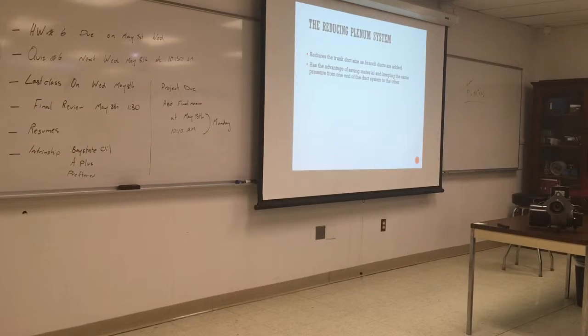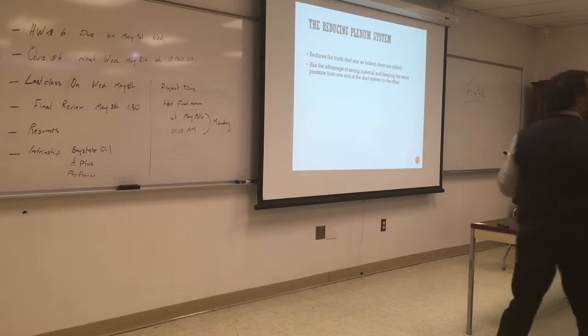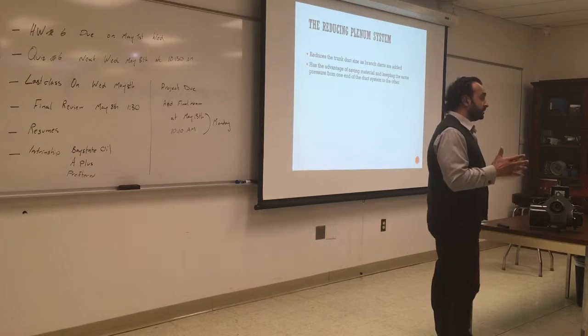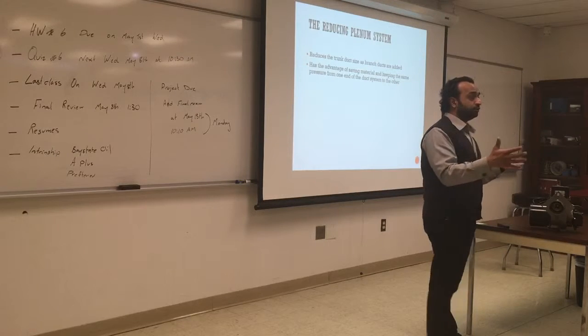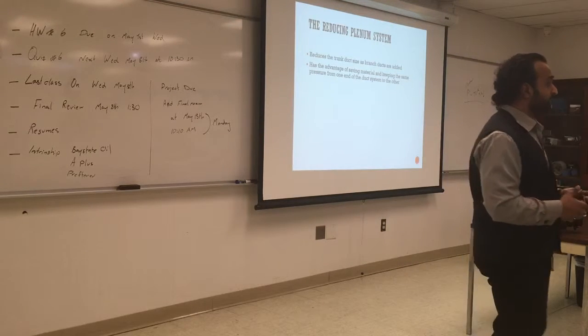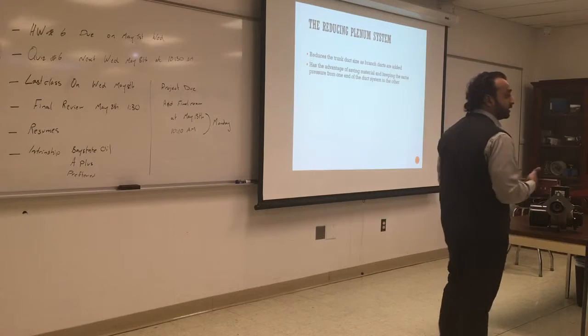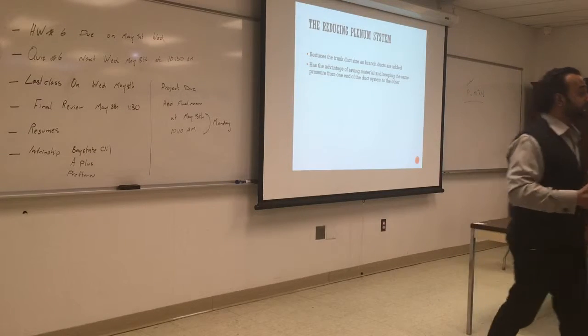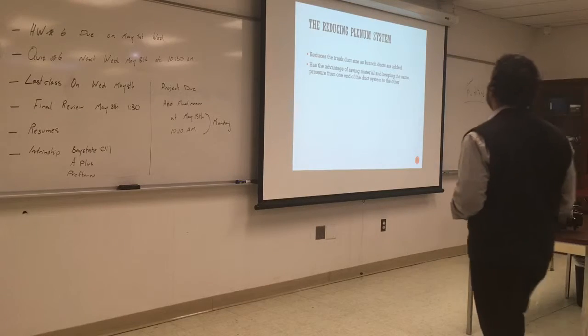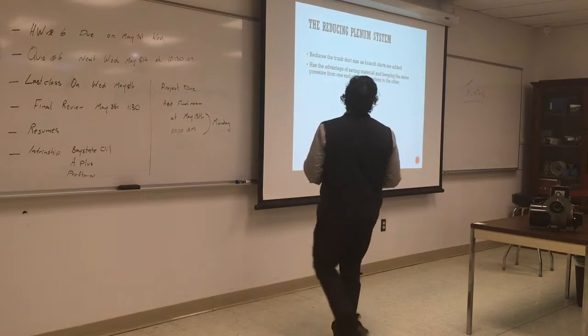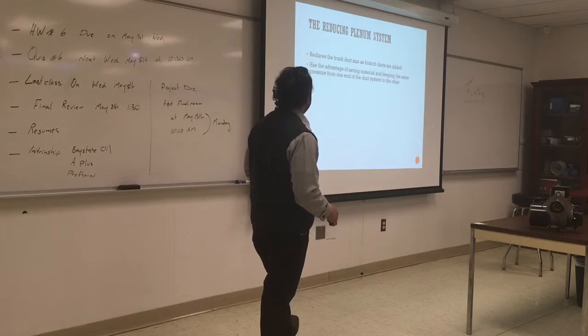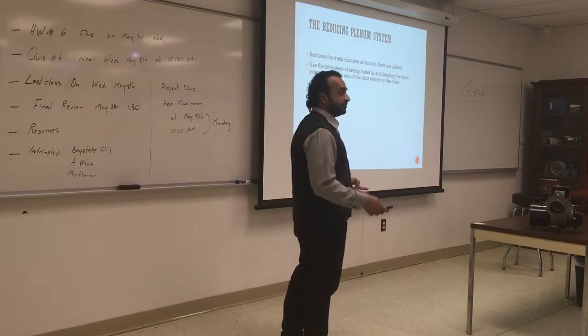How come we don't do that with water? Because you put a pump in? Yeah, what else? What is the difference between water and air? Compressible. So compressibility: as we go further, air will be less compressible, and you might compress in the beginning and it spreads out and you'll lose pressure. With water, the pressure has a different equation and it's not compressible, so whatever comes in from this place goes out without any kind of compressibility. So it has the advantage of saving material and keeping the same pressure from one end to another. And as we reduce, we save more material.